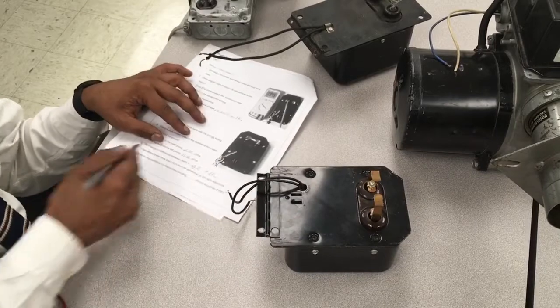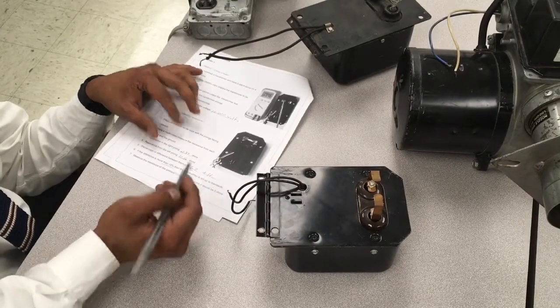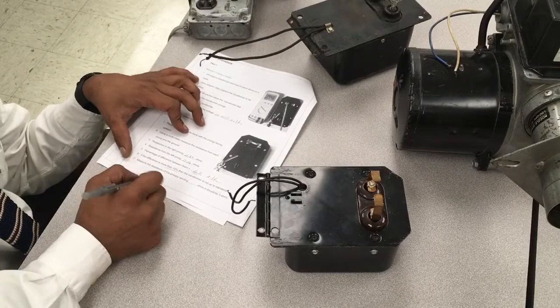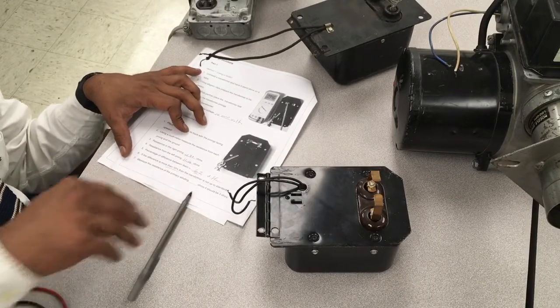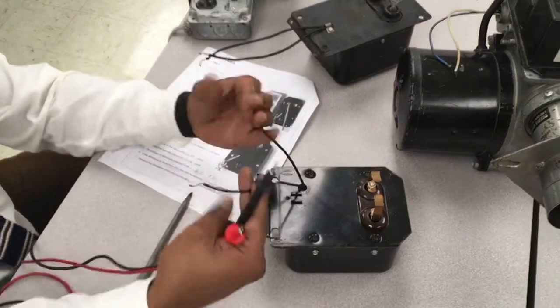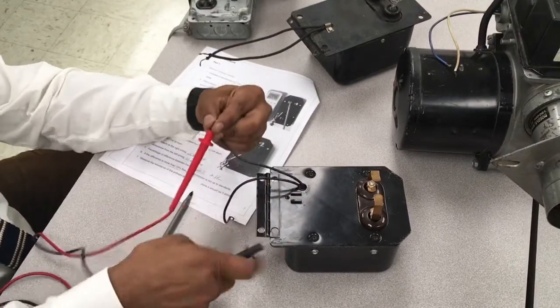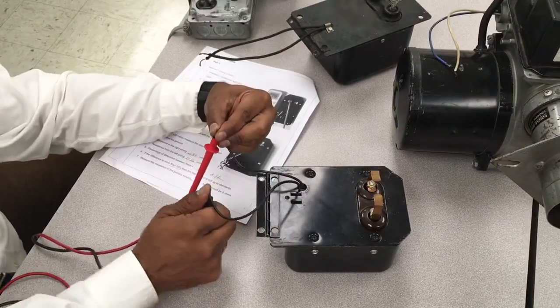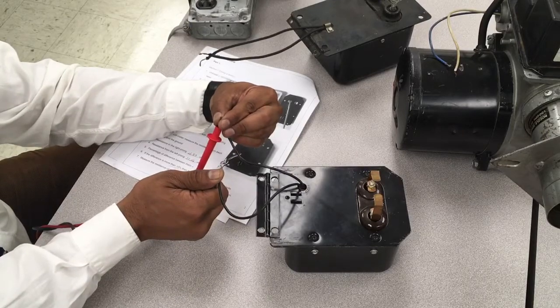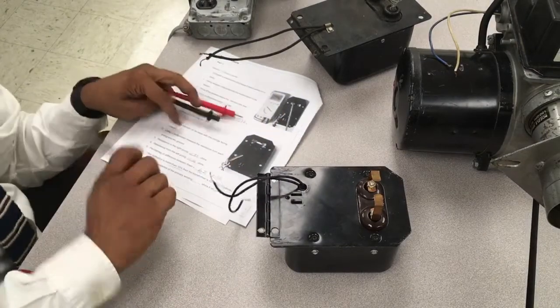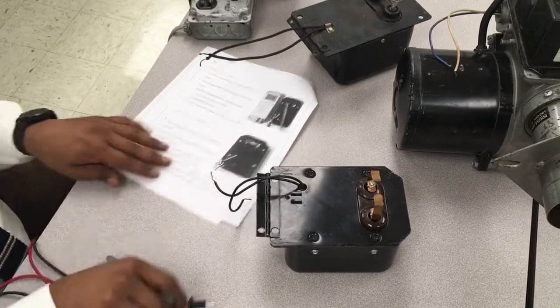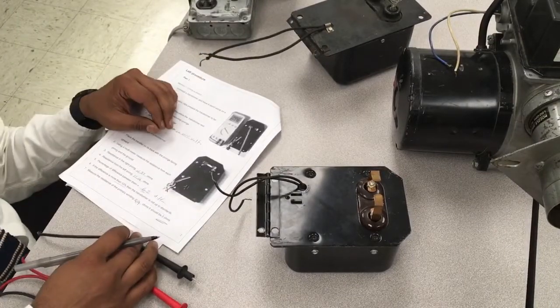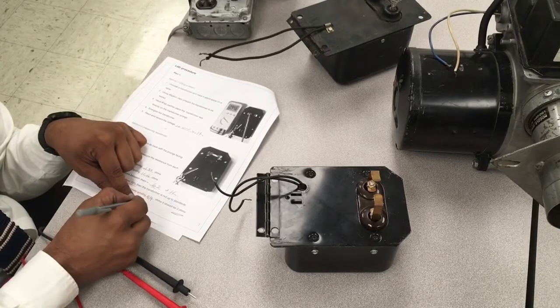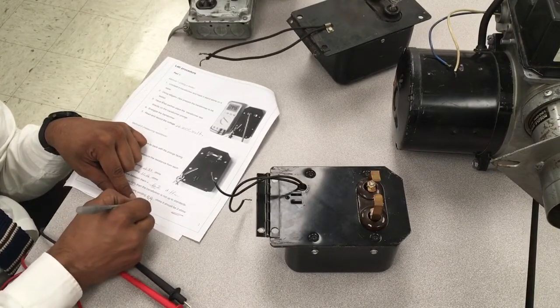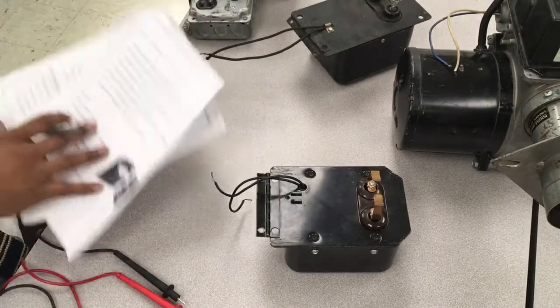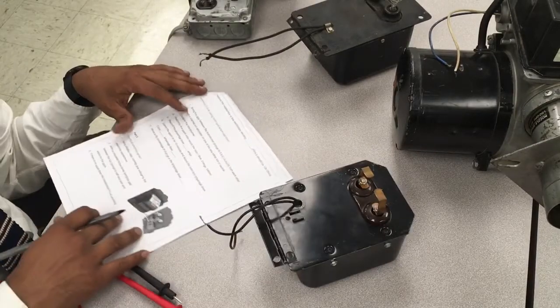If the difference is more than 10%, then the transformer is not up to standards. Step 7, measure the resistance of the primary winding. This is the primary because it's getting 110 volts. So we'll measure this to the primary, and I'm getting 3.9 ohms. It should be 3 ohms. Within 10% it's okay, so this is a little bit too high. 10% of 3 ohms should be 3.3, so it's a little on the high side. So we can tell that this transformer has been used for a long time.